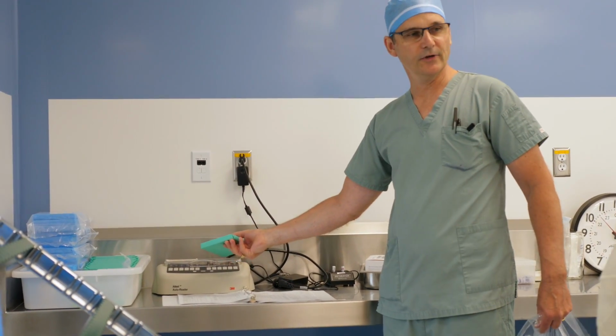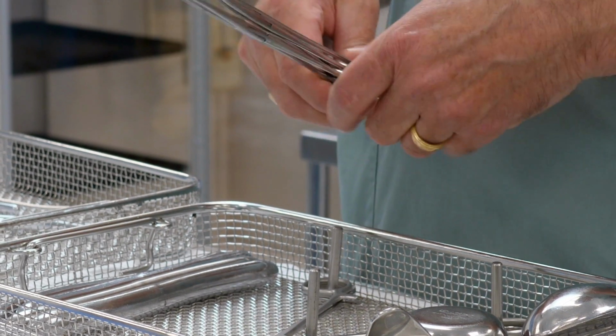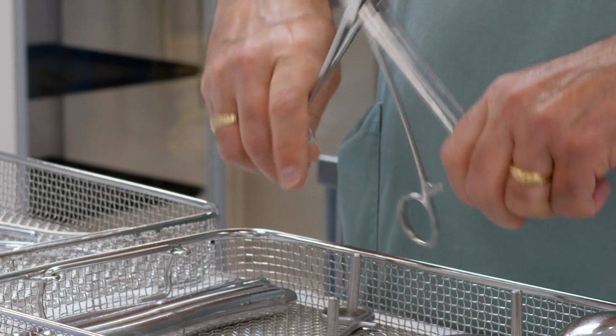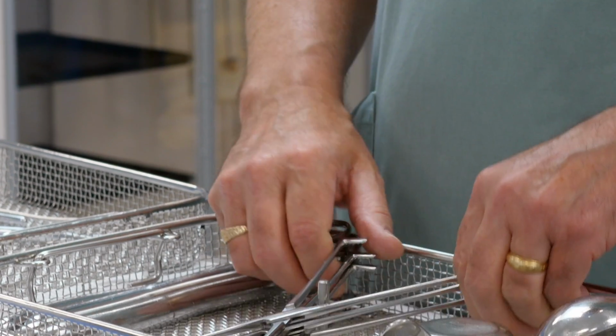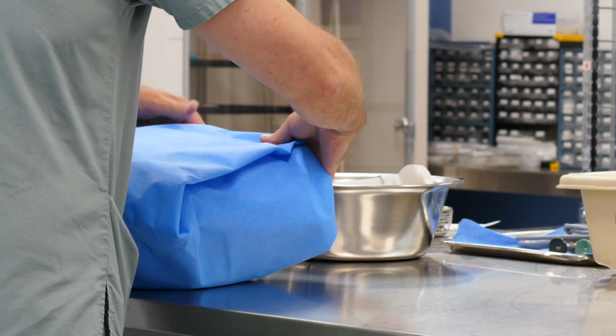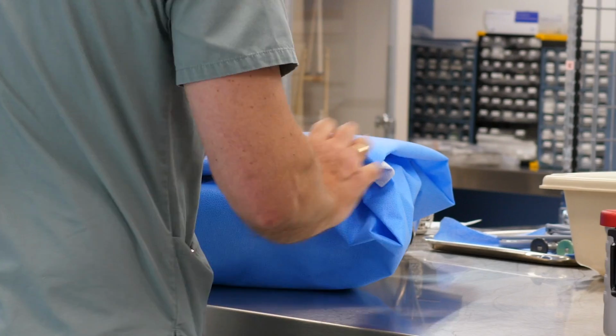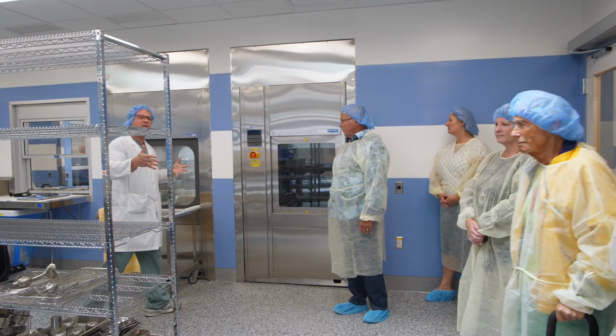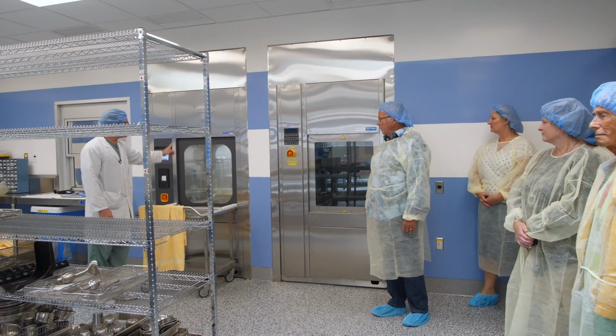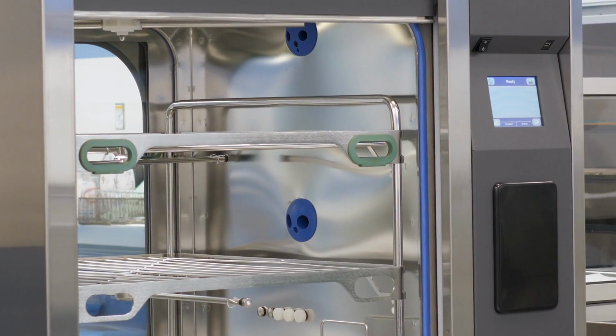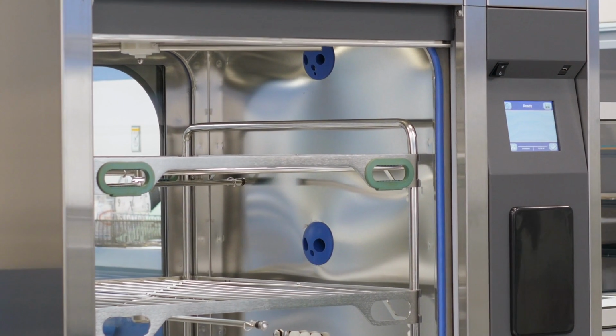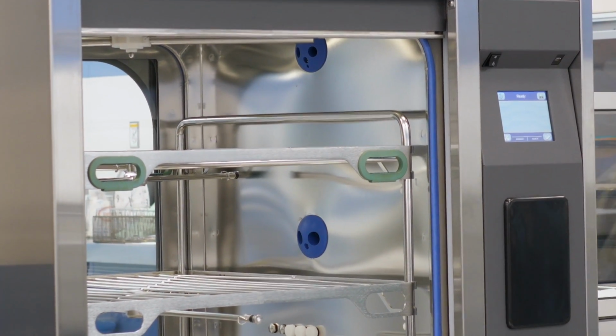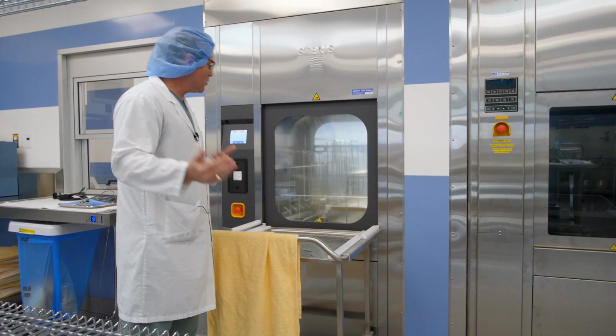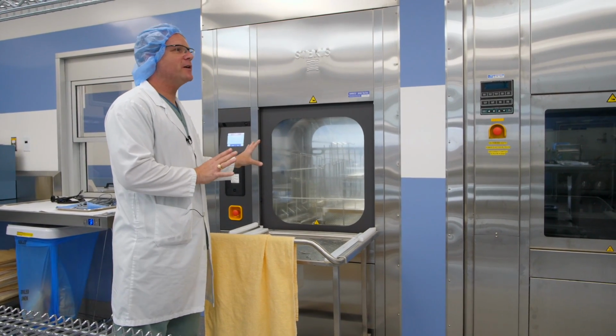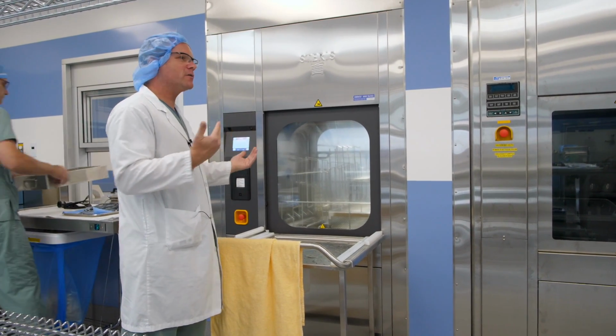Fantastic. So this is Todd. He's our lead hand in our MDRD, and he keeps the quality of the instruments leaving the sterilization side, the clean side, at a very, very high level. The process from Todd's perspective on this side is once things have come through the washers, these washers are specifically designed to prevent cross-contamination. So if this door opens, that door is closed. If that door is open, this door is closed, and you can't open both doors at the same time, as well as you can't pass instruments back through. So if you have something you don't like, you can't pass it back through. It actually prevents you from doing that to make sure there's no risk for cross-contamination.